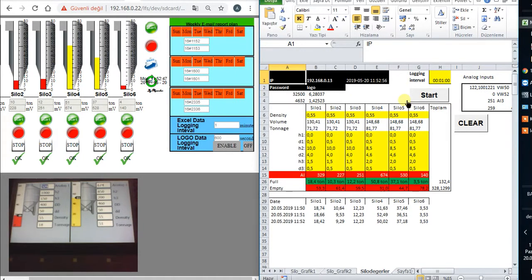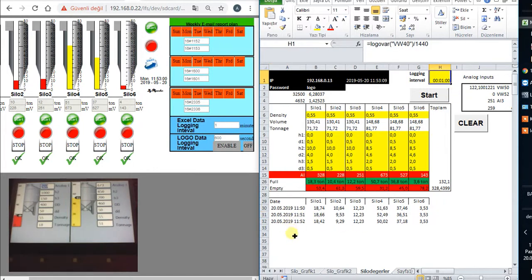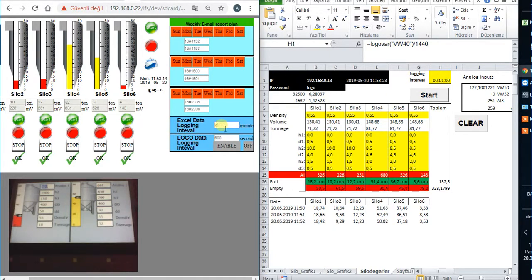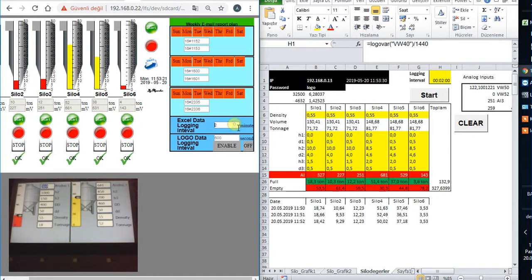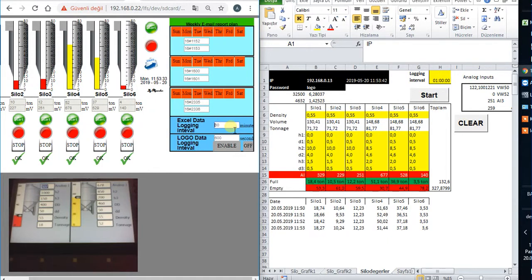This Marker 4 is also data logging, starting the data logging of the Microsoft Excel. With this time interval, these values are written to here. And this time interval is also controlled from here. This is one minute. If I write here two minutes, the time interval is changed to two minutes. If you write 60 minutes, it's changed to one hour. You must write your time in the minute: 180, 3 hours.